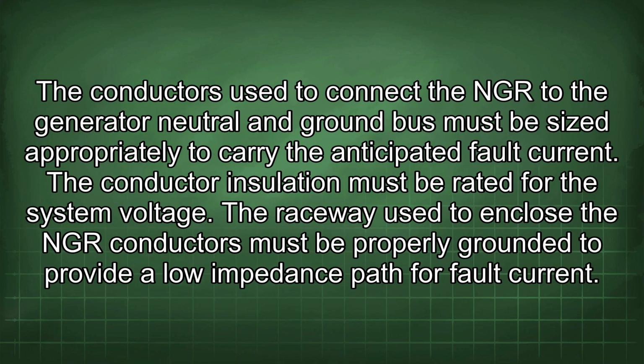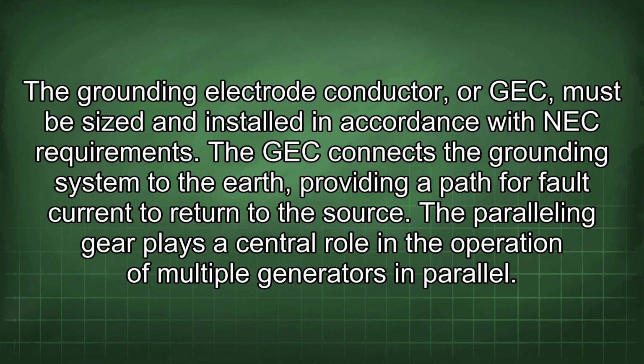The conductors used to connect the NGR to the generator neutral and ground bus must be sized appropriately to carry the anticipated fault current. The conductor insulation must be rated for the system voltage. The raceway used to enclose the NGR conductors must be properly grounded to provide a low impedance path for fault current. The grounding electrode conductor, or GEC, must be sized and installed in accordance with NEC requirements. The GEC connects the grounding system to the earth, providing a path for fault current to return to the source.